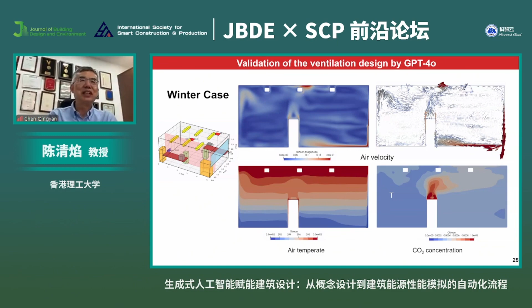For anyone who has studied building energy transfer, heat gain is not cooling load, because the building thermal mass will absorb the heat gain, and then there will be delay and decay, etc., and release back. Normally the cooling load is smaller than the heat gain. That's the first conceptual reason why it is wrong.